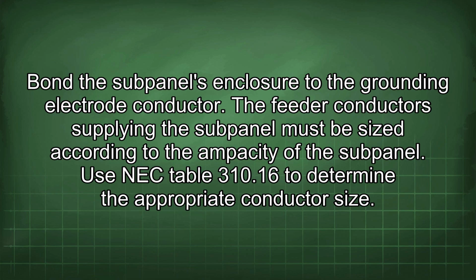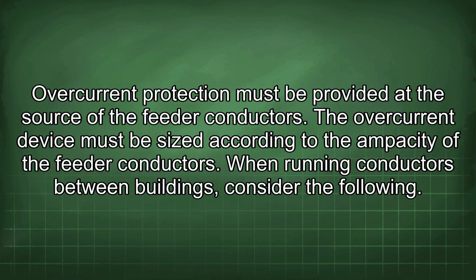The feeder conductors supplying the subpanel must be sized according to the ampacity of the subpanel. Use NEC Table 310.16 to determine the appropriate conductor size. Overcurrent protection must be provided at the source of the feeder conductors. The overcurrent device must be sized according to the ampacity of the feeder conductors.